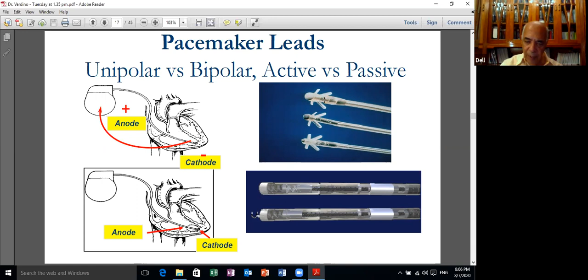Now this is the strength duration curve, and I'd like you to concentrate with me. This shows the relation between the duration of the pulse, or the pulse width, and the stimulation threshold in volts. If you look here, as you go to infinity with the pulse width, or a very wide pulse width, the activation threshold in volts is called the rheobase. So the rheobase is a stimulation threshold. If you double the rheobase, and you jump here, and then look at the time at which double the rheobase activates, this is called the chronaxie.